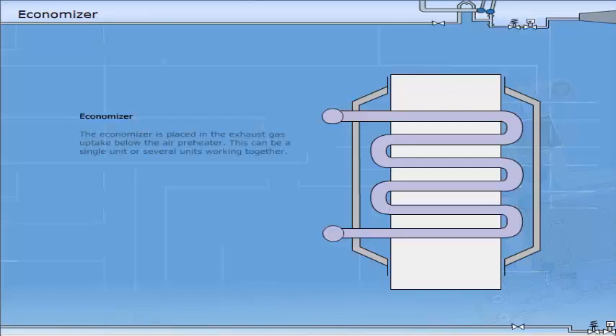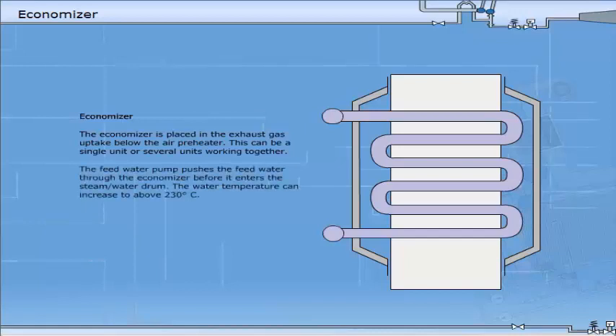The economiser is placed in the exhaust gas uptake below the air preheater. This can be a single unit or several units working together. The feed water pump pushes the feed water through the economiser before it enters the steam water drum. The water temperature can increase to above 230 degrees centigrade.